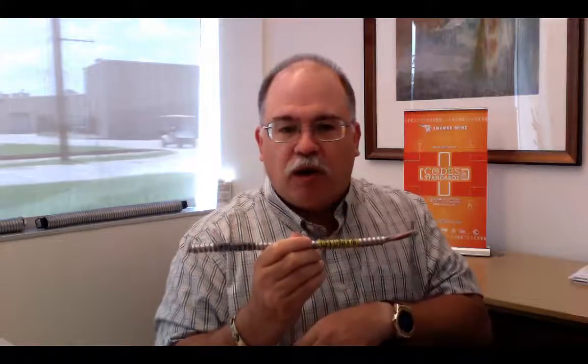It helped us at a glance. When I walked into a kitchen, I knew that it had to be done in yellow. This does the same thing. Maybe you're doing multi-family dwellings, a high rise of apartments, and all the kitchens have to be done in 12 to a minimum of two small appliance branch circuits. At a glance, I can make sure that they use 12 wire in those areas.